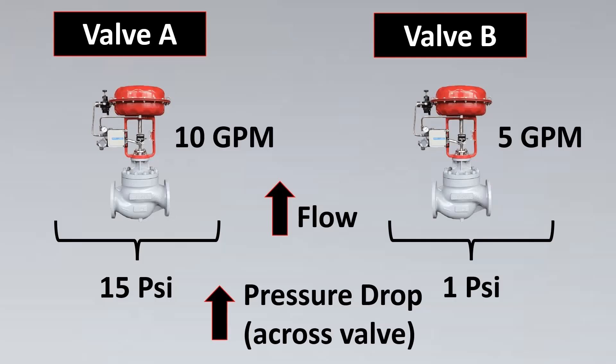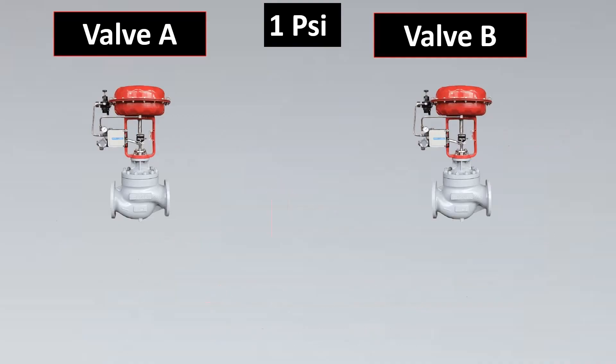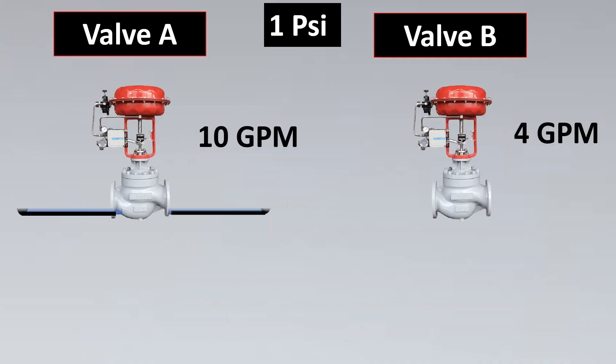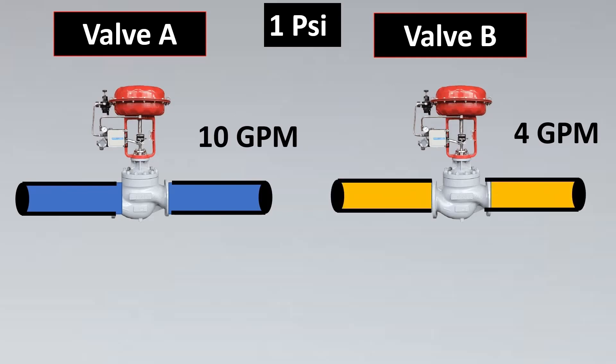So if we want to compare two valves' flow capacity, we have to keep them under the same pressure. Let us take a standard of 1 PSI pressure drop across both valves. Now measuring again, I see the flow through the first valve is 10 GPM and the flow through the second valve is 4 GPM.